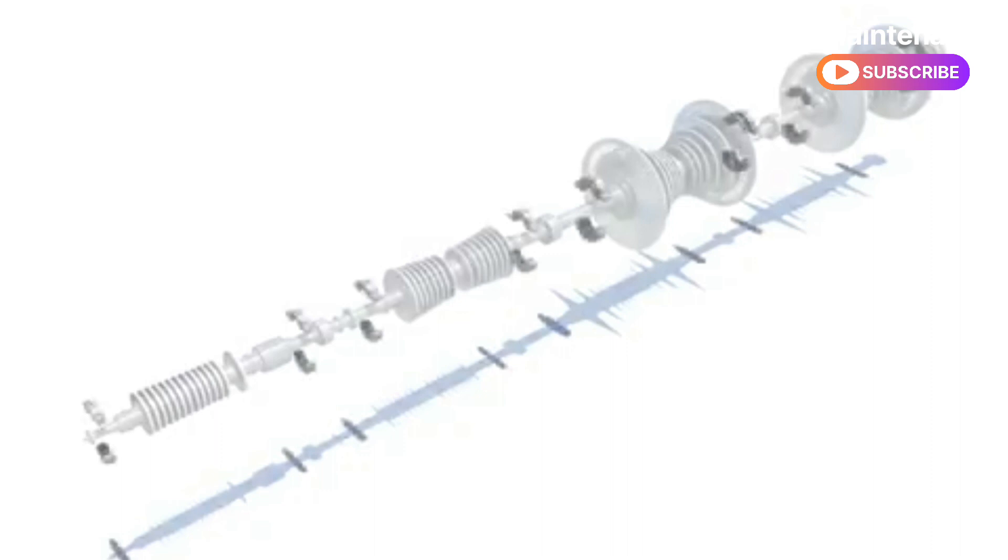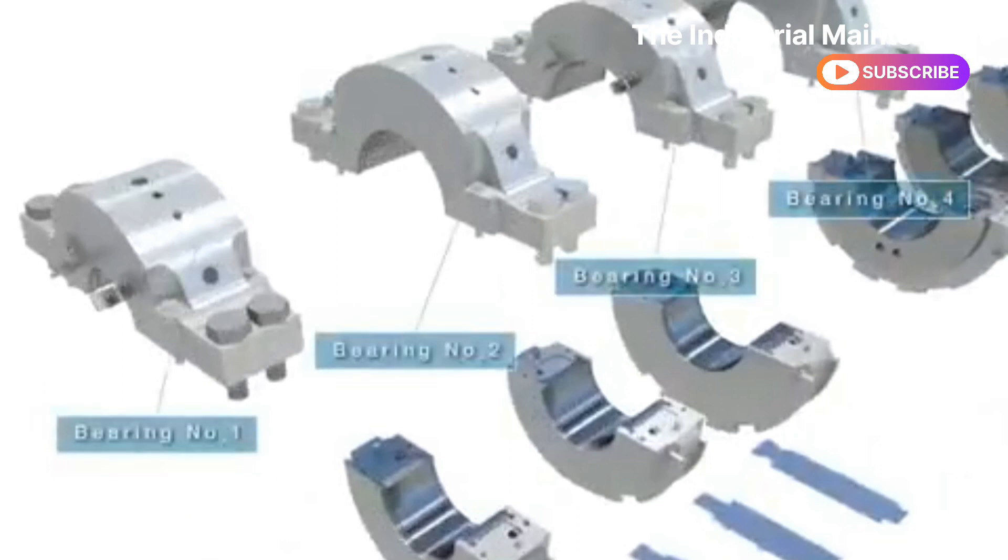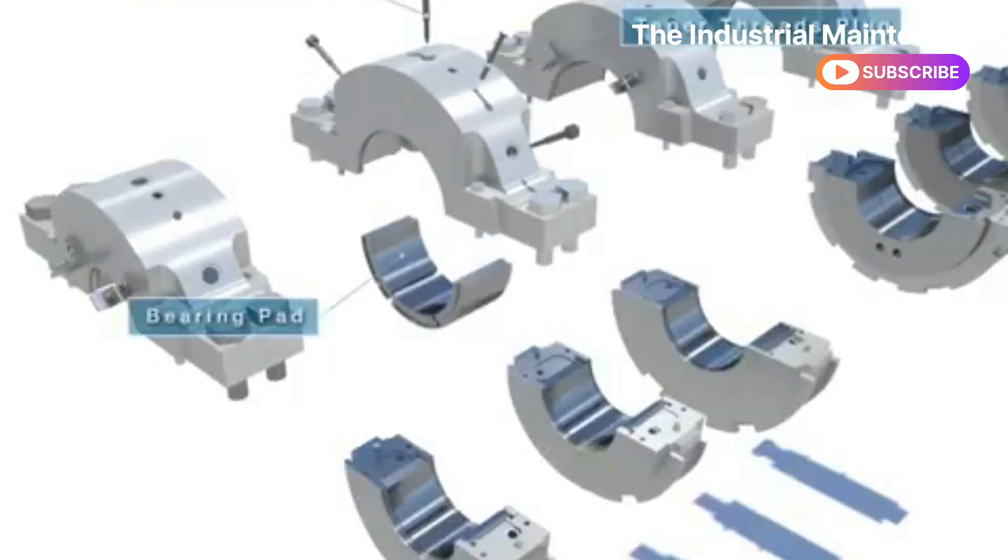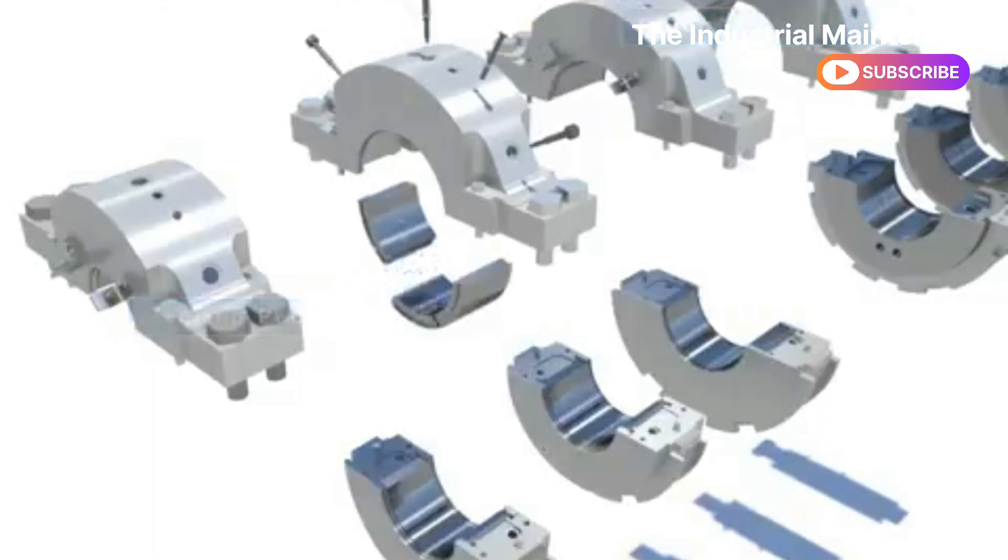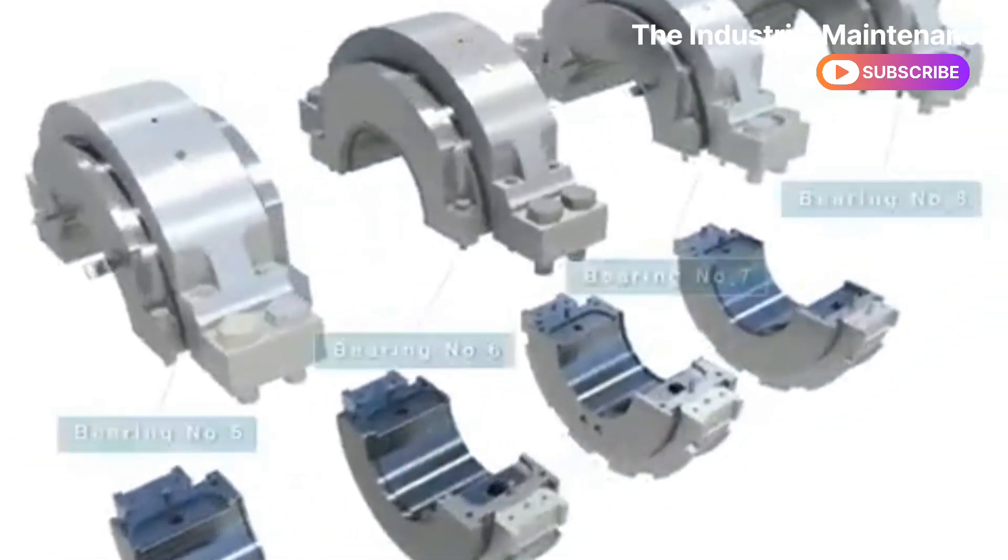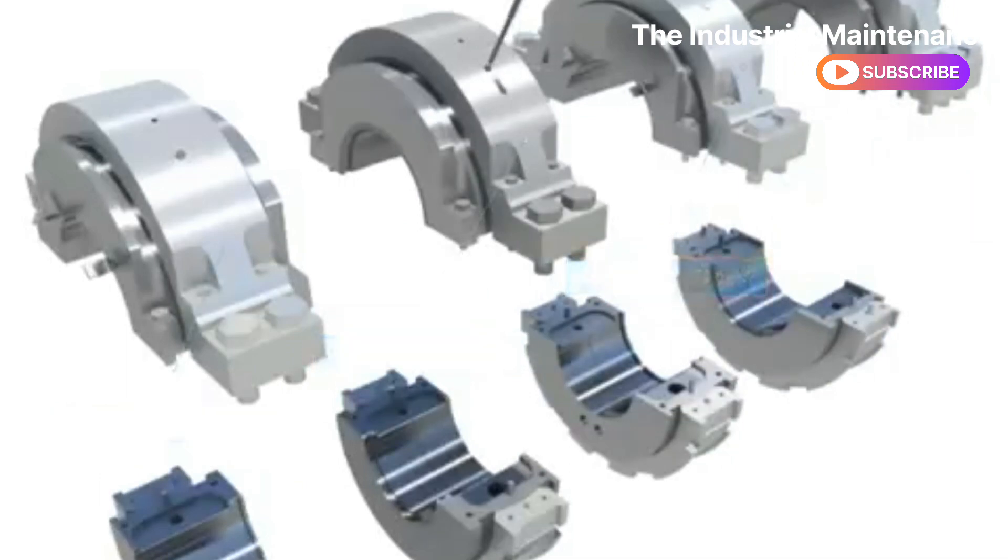The bearing is an equipment which sustains the weight and thrust of the turbine rotor. Number 1 to number 4 bearing consists of double tilting pad type. Number 5 to number 8 bearing consists of elliptical type.